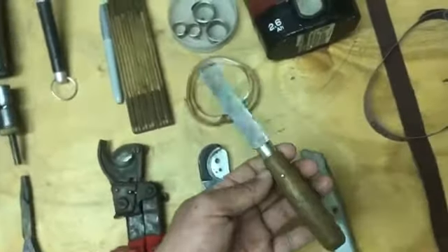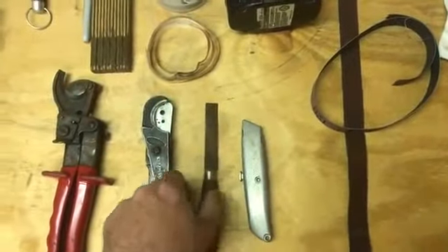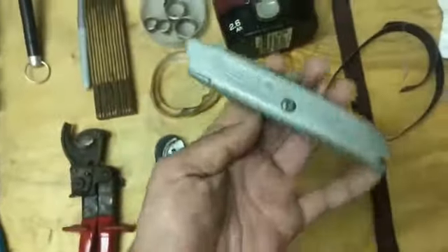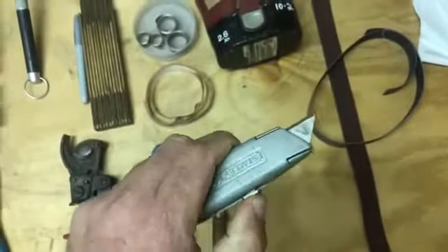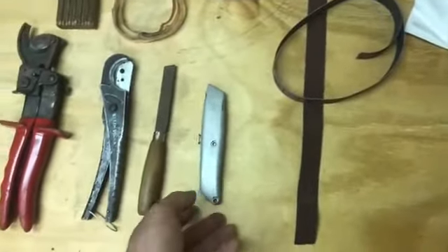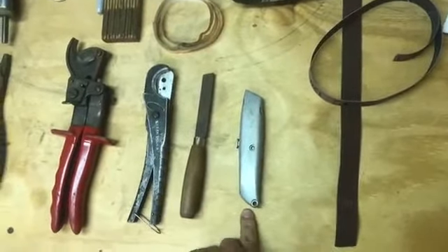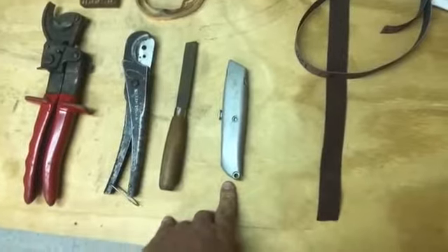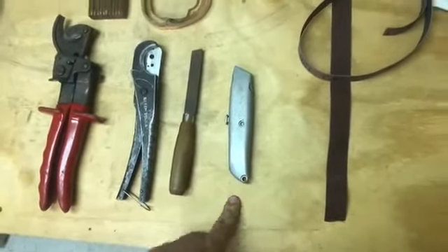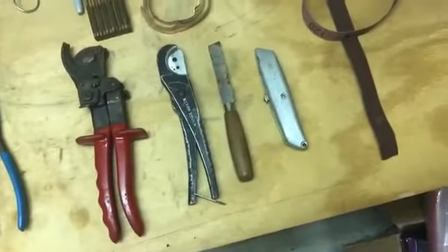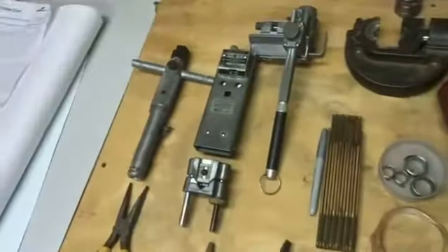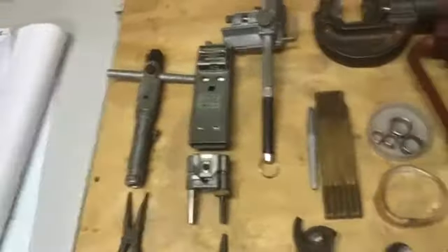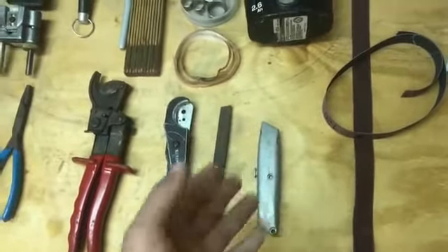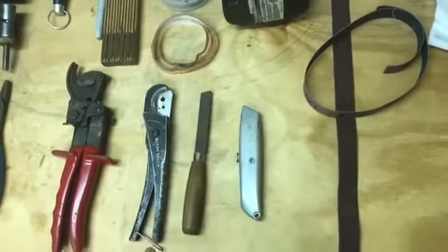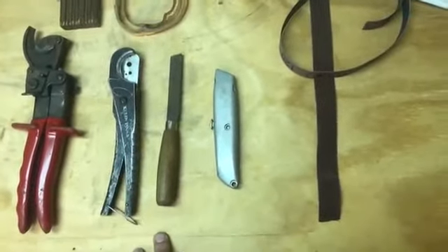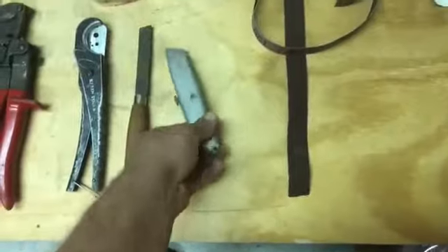This is a shoe knife that we use, a typical splicer's knife. We use that very frequently. And then this is a Stanley, just basic Stanley 99 razor knife, retractable blade. I'll use this every once in a while. Some terminations dictate, just because of the build of the cable or different factors, that you almost have to use a razor knife. Some guys will actually perform the entire splice with a razor knife. I prefer to use the specialty tools to do that. It's just a little less risk factor. Not saying you can't do it with a razor knife. It just takes a lot of knife practice, and it's very easy to mess up if you don't have the appropriate practice. But we may end up using this, we may not.